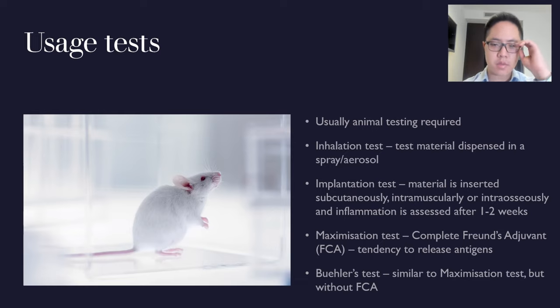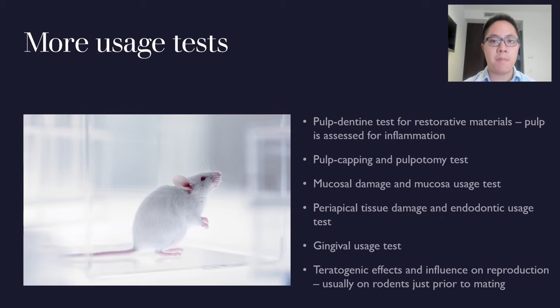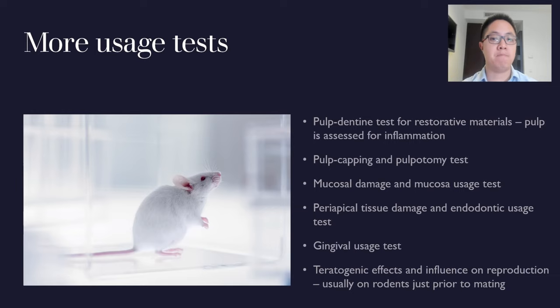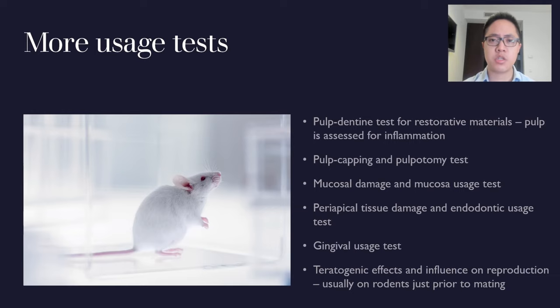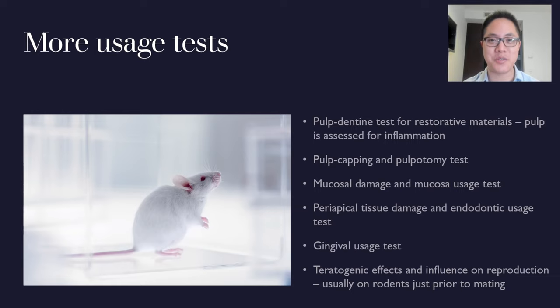Implantation tests involve the material being implanted in an animal or into an area, and the degree of inflammation is assessed afterwards. Specific to teeth, there are pulp dentin tests for restorative materials — using an animal tooth like a rat tooth, a restorative material is placed in a prepared cavity and after extraction the pulp is assessed for signs of inflammation. Very similar in principle to pulp capping and pulpotomy tests. There's a lot of testing that goes into placing materials on oral structures.